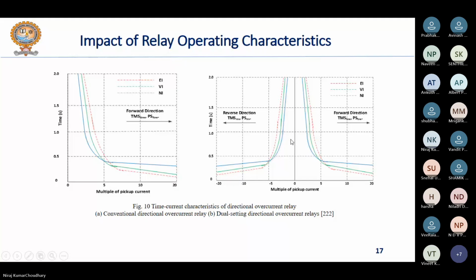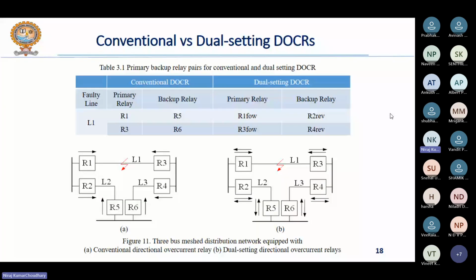Suppose there is a relay R1, then the relay R1 will have a particular TMS and PS setting, that is time multiplier setting and plug setting, for the forward direction of fault current. And similarly for the reverse direction of fault current, for the same relay R1, there will be TMS reverse as well as PS reverse. Similarly for the three types of characteristics, normal inverse, very inverse and extremely inverse, you can see the different IDMT characteristics. Here in this slide, you can get better insight into the two types of characteristics.